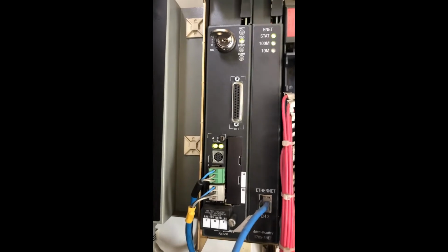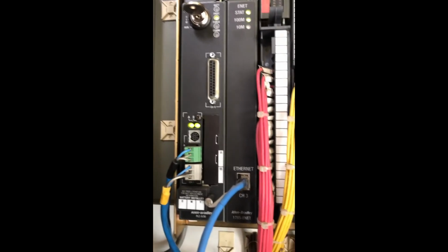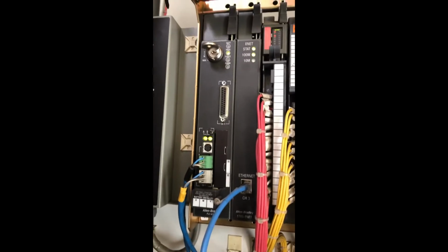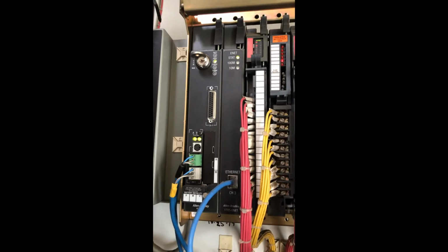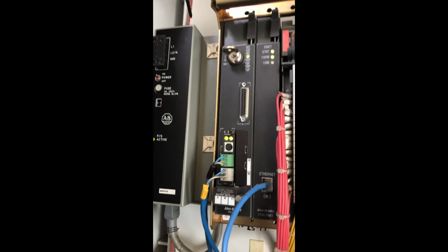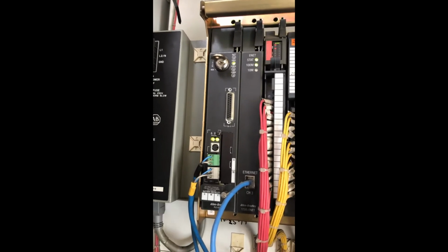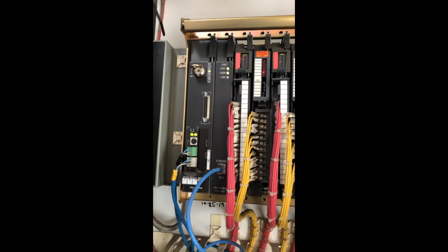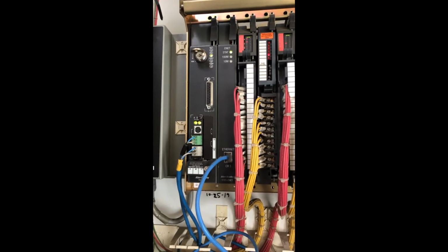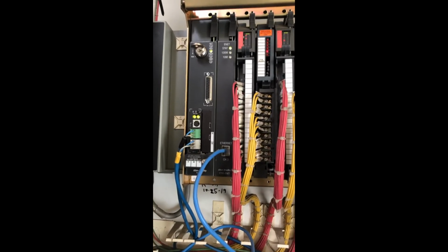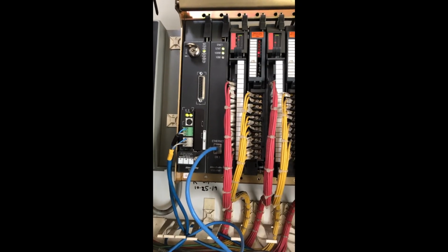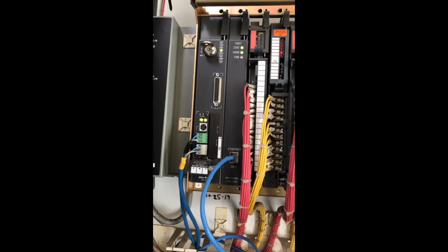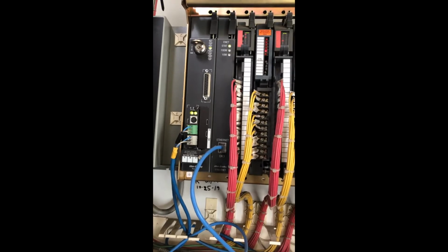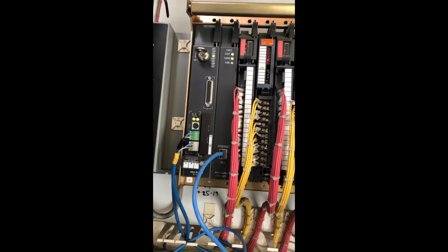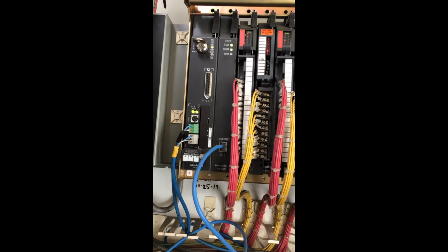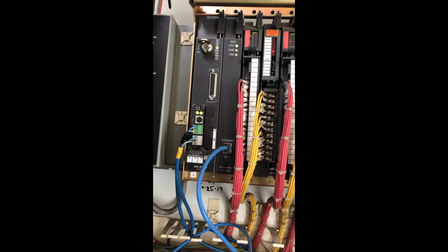This module on the left here is our PLC. It has an Ethernet connection that allows it to communicate with the main SCADA computers and also to communicate with other PLCs. They all kind of tie together and work together. For example, this PLC here gets a signal from that HMI we were looking at just before over the dewatering building, and then through the Ethernet connection goes to another PLC where the sludge dewatering pumps are actually located, and then from an analog output over at the other PLC it's actually commanding the sludge dewatering pumps depending on what the operator wants from here.